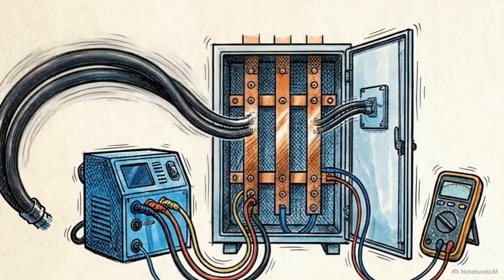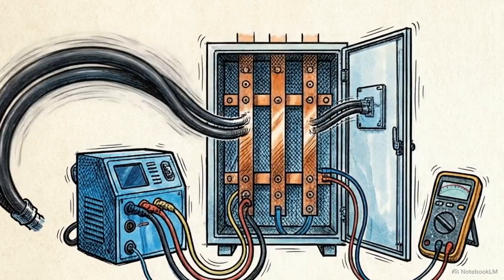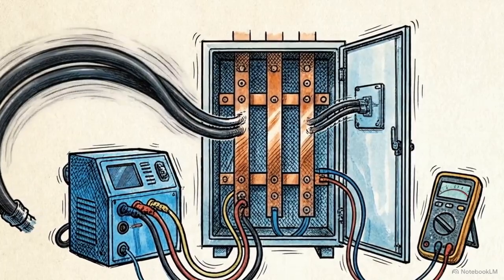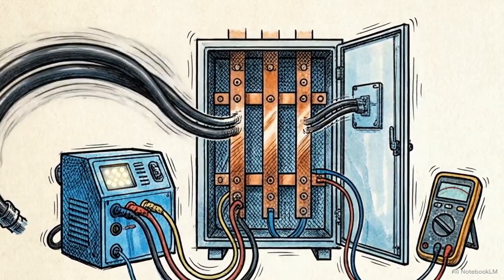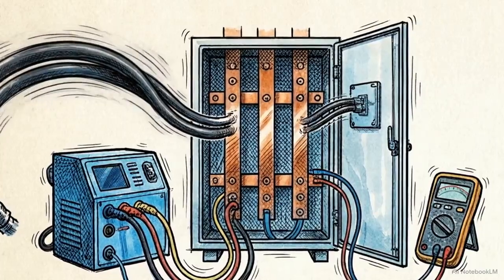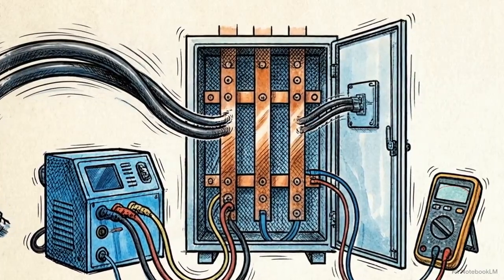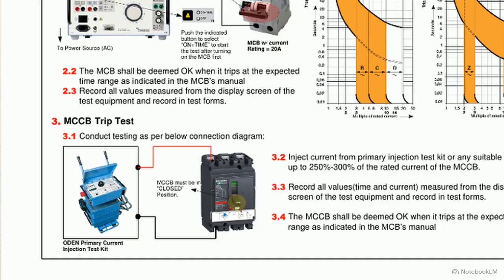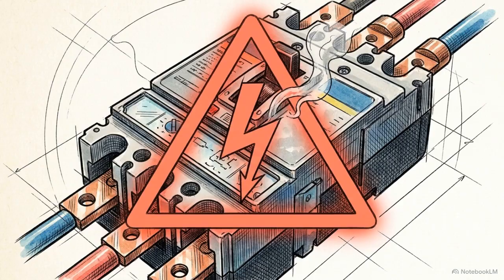Molded case circuit breakers, or MCCBs, require significantly higher testing parameters. These devices handle larger electrical loads coming directly off the main distribution feeds. To test them, engineers shift to primary current injection testing. This setup uses a heavy-duty unit like the Oden test kit shown here to push massive amounts of actual current directly through the breaker's physical poles. The protocol dictates injecting a simulated fault, driving between 250 and 300% of the breaker's maximum rated current straight into the system.